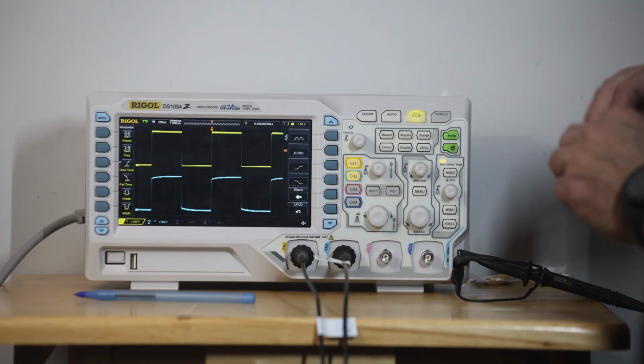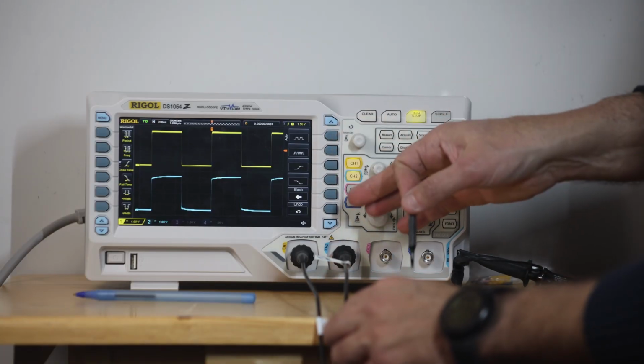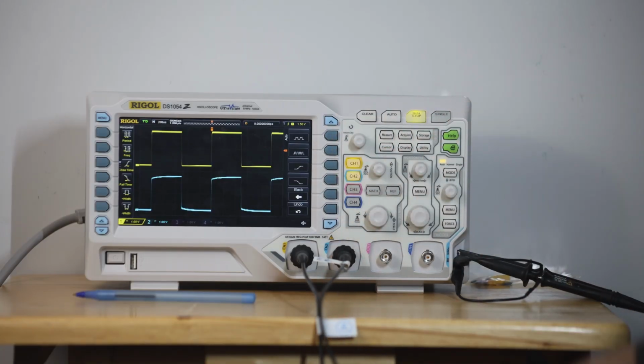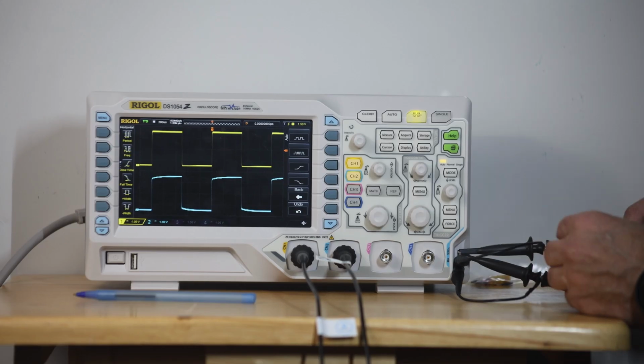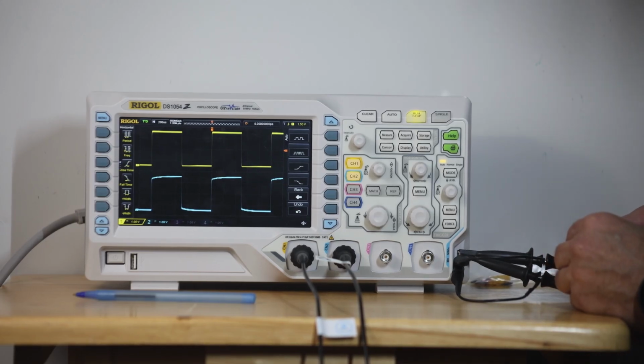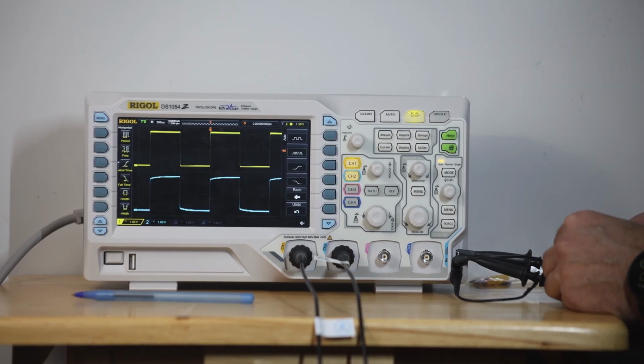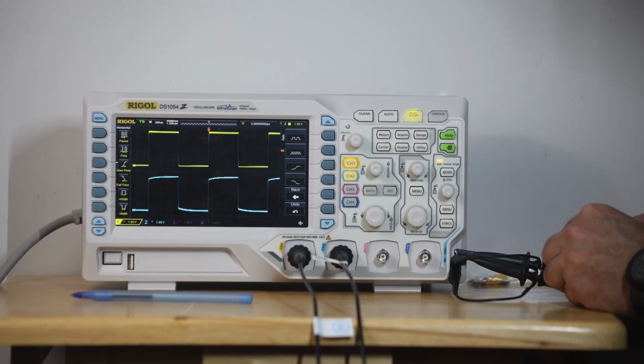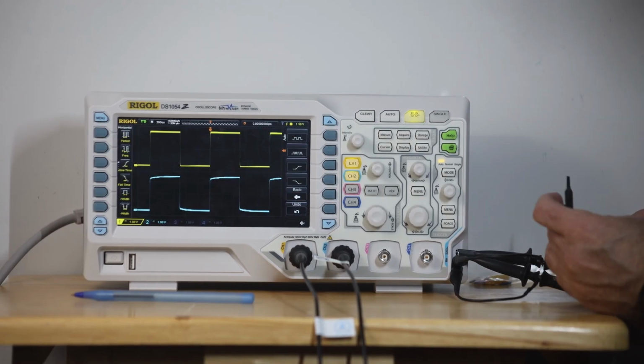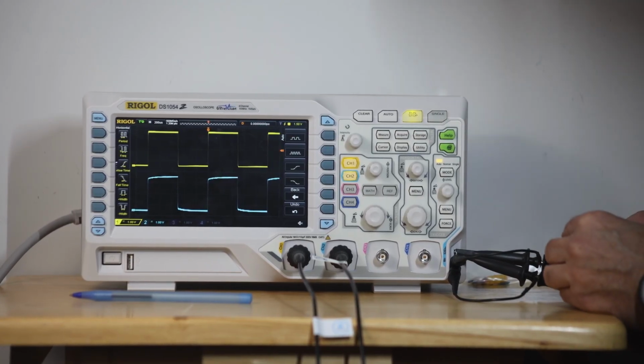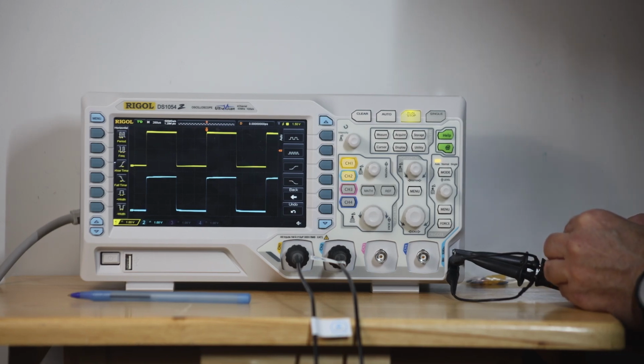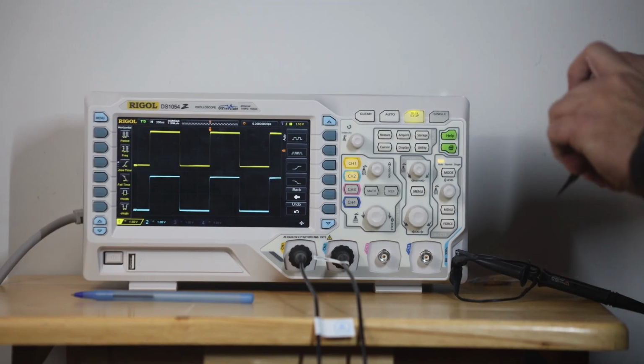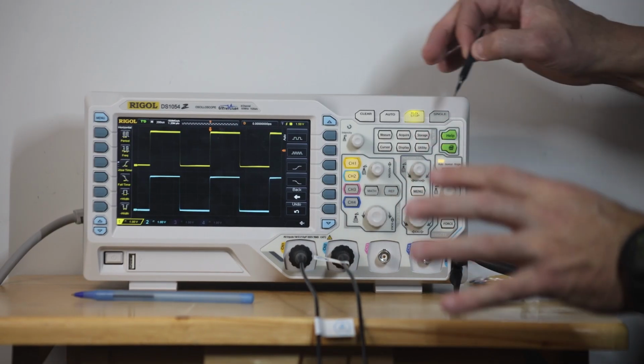We'll say that's calibrated. Now we want to do the same for channel 2. So I'll grab the channel 2 probe. I'll find that set screw. And we'll adjust it. And let me line up the set screw with the screwdriver. All right, starting to move a little bit. And right about there. Okay, so now we have both probes calibrated.